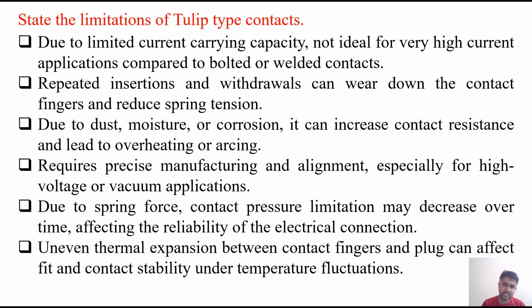It requires precise manufacturing and alignment, especially for high voltage or vacuum applications. Due to spring force, contact pressure may decrease over time, affecting the reliability of the electrical connection. Uneven thermal expansion between contact fingers and plug can affect the fit and contact stability under temperature fluctuations. So these are several disadvantages of tulip type contacts.